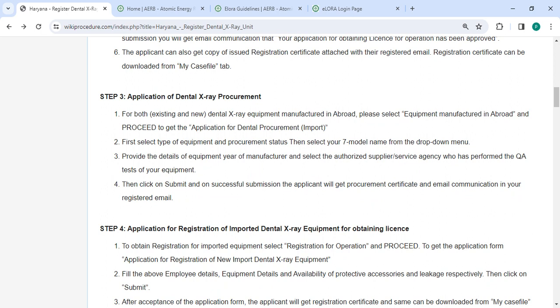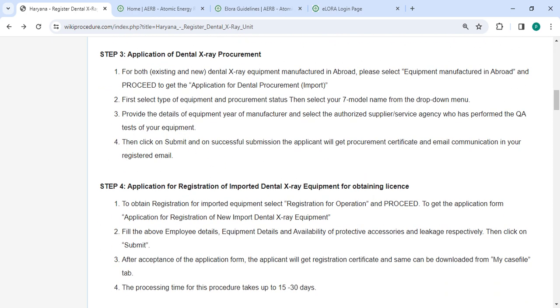For dental X-ray equipment manufacturers abroad, please select 'Equipment Manufacturer Abroad' and proceed to get the application for dental X-ray. First, select the type of equipment and procurement status, then select your system model name from the dropdown. Provide the details of equipment, year of manufacturing, and select the authorized supplier or service agency who has performed the QA test of your equipment, then click submit.